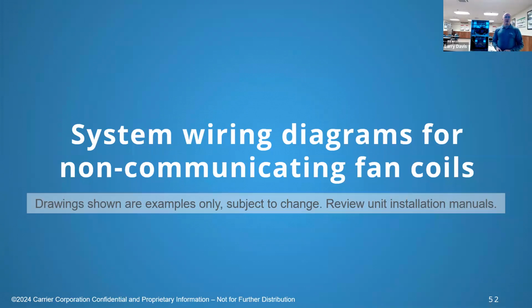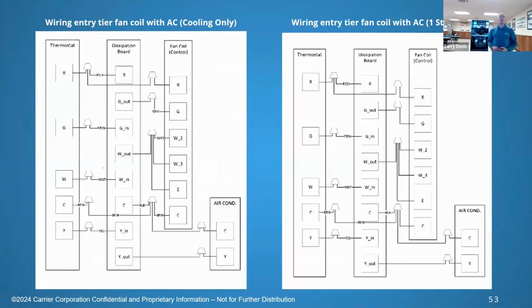Let's look at some wiring diagrams for these new systems with the dissipation control. So here you see, we've looked at this before. It's a standard fan coil with a straight AC unit. Your commons all tied together. Your call for heat from the thermostat goes through the dissipation board, and then you have the heat call out that goes to your different stages of heat for the fan coil.